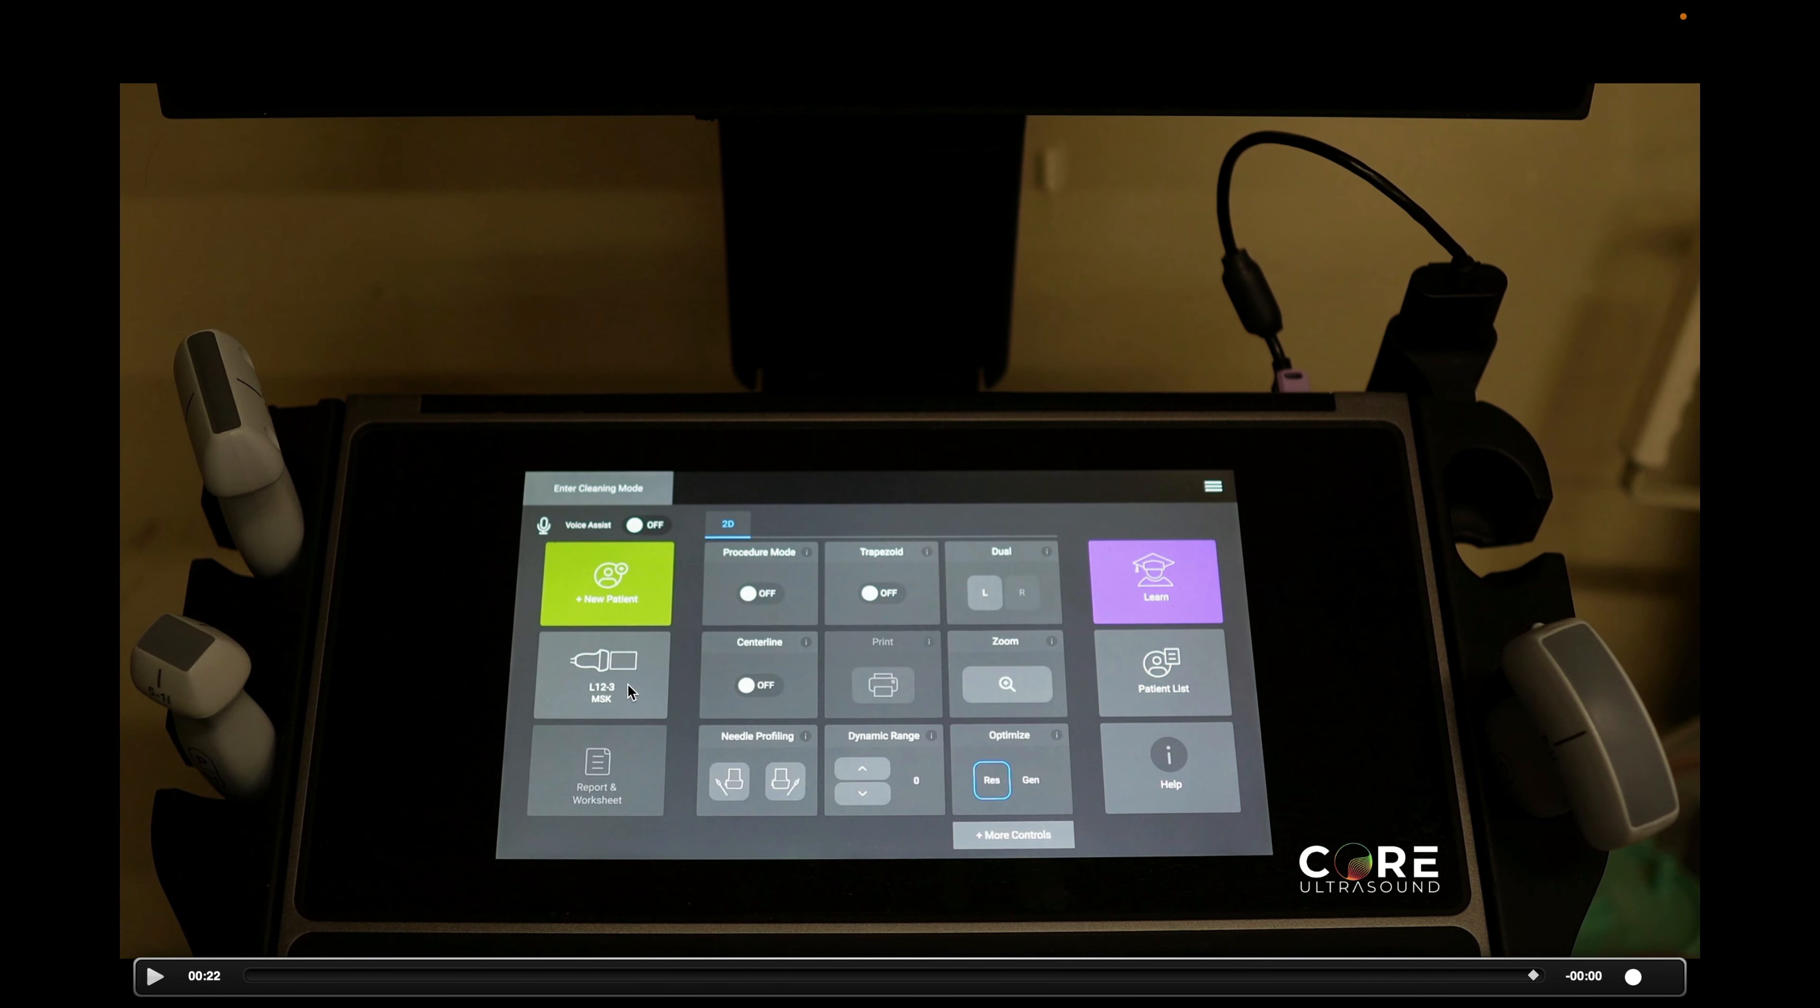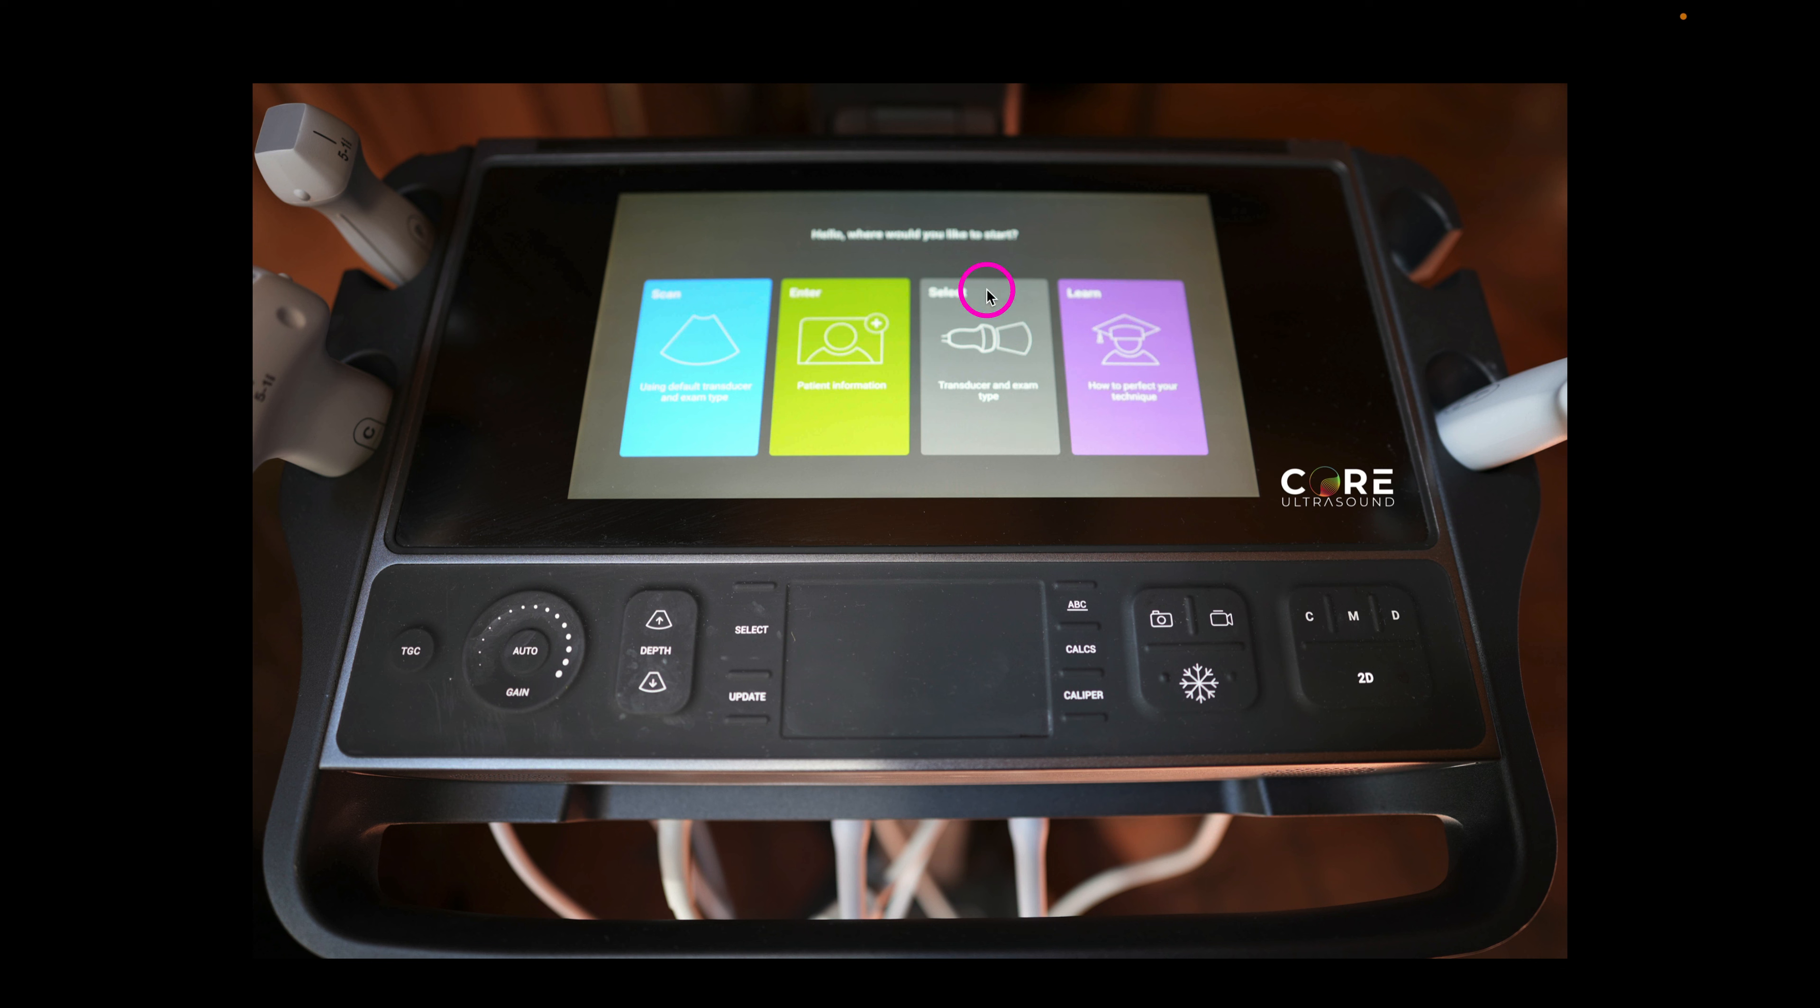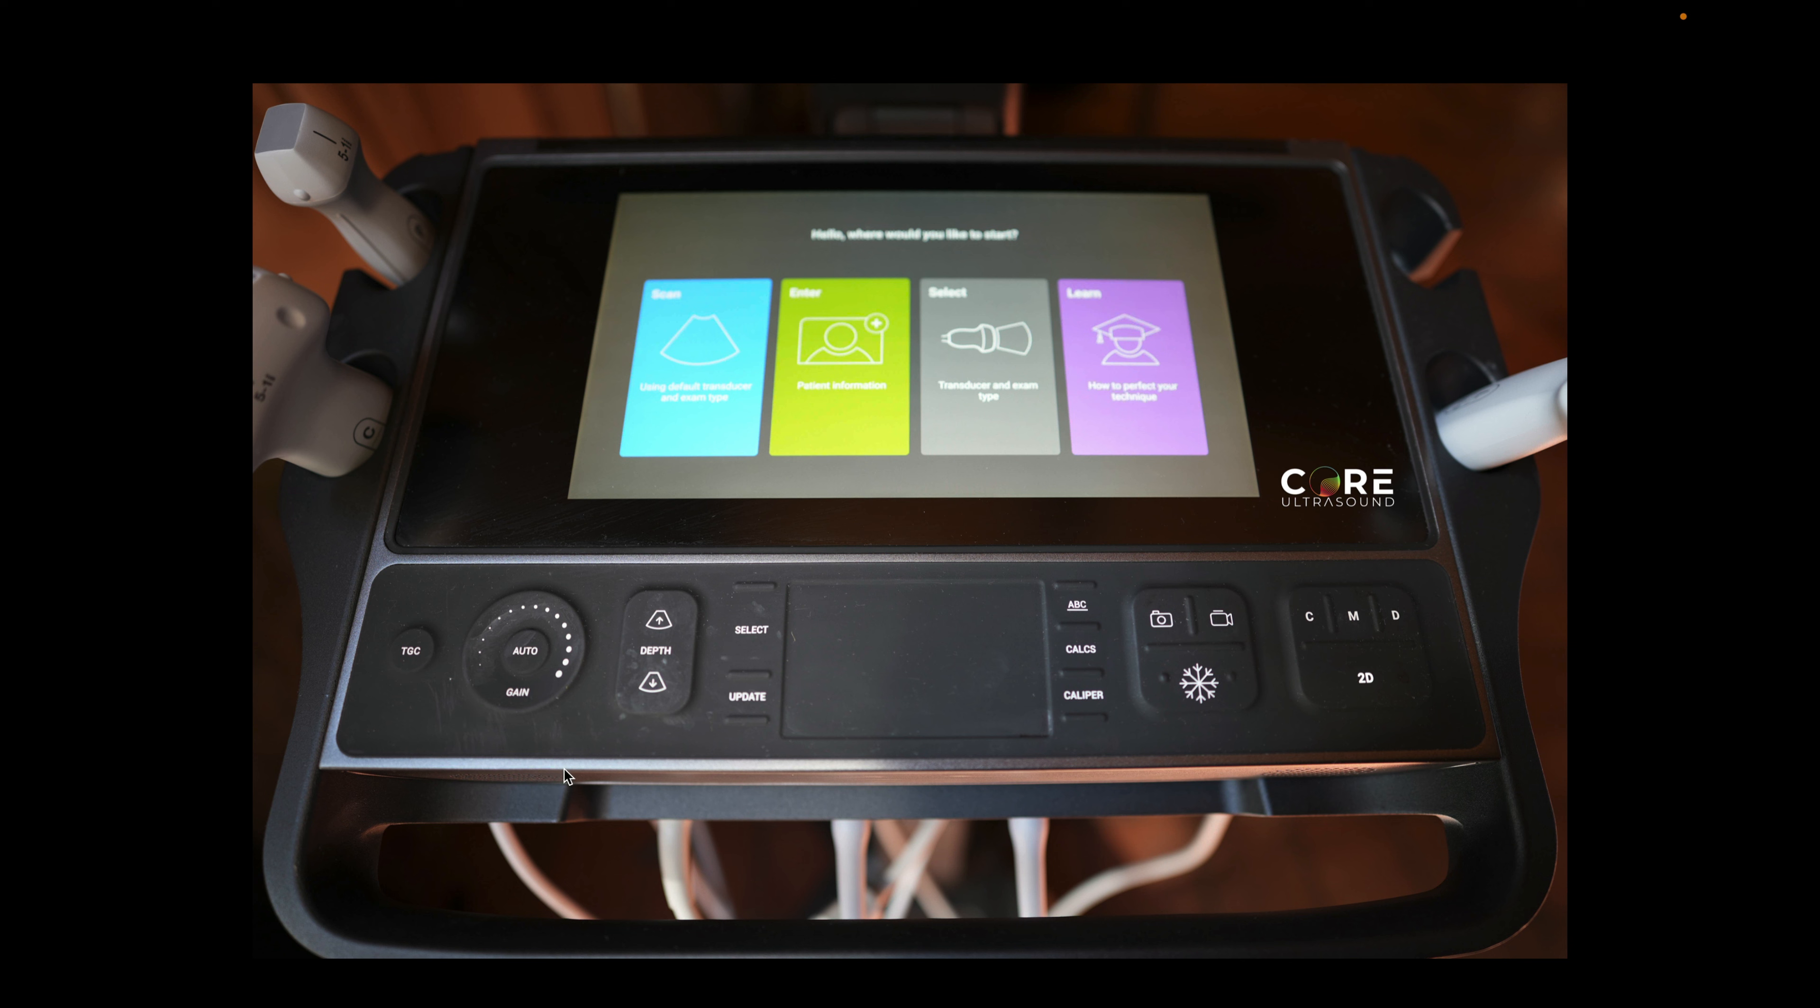Some basic machine operation. Next, I've zoomed out just a bit. This was that touch screen that we were looking at earlier. And over here, we have physical buttons. We have gain. We would put our finger here and kind of slide it this way or back this way. That'll turn up or down the gain or the brightness of that image. We can change the depth by hitting the up to increase depth or down to decrease depth.